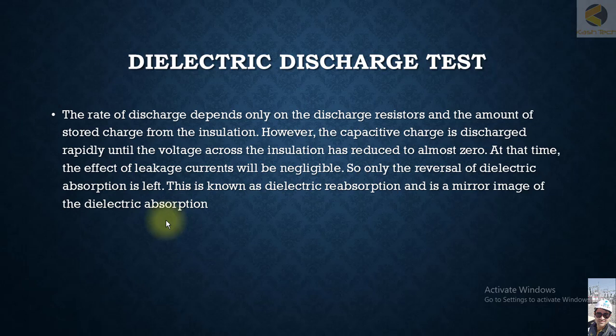When doing a discharge test, the leakage current is negligible and there is only discharge current. Normally in dielectric testing you get absorption current, but now that current is decaying — so it is the reabsorption current that you are monitoring.